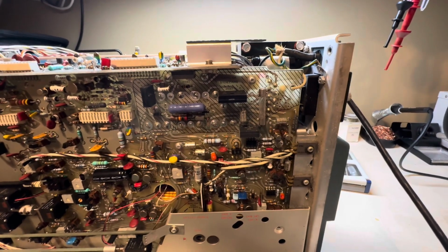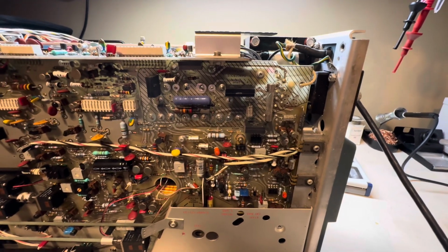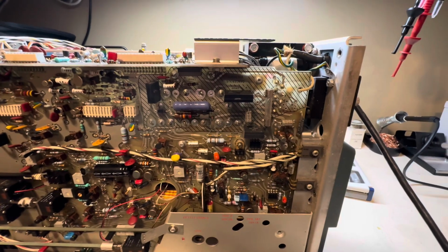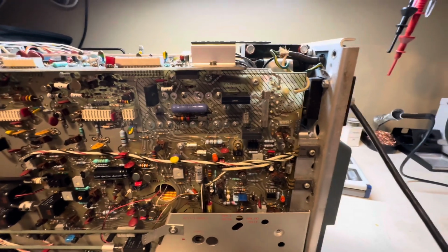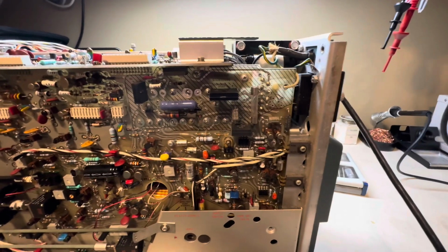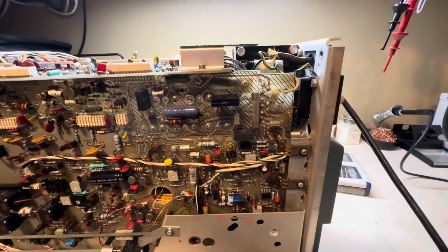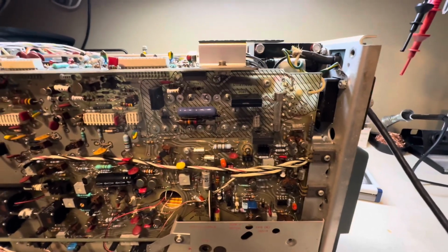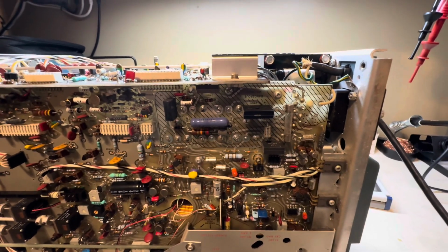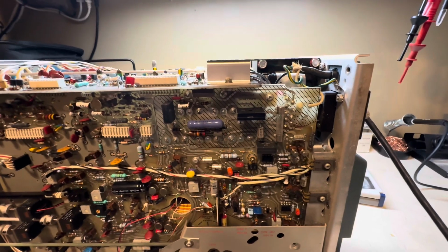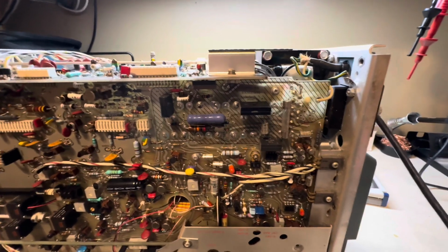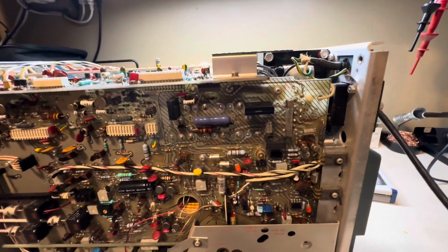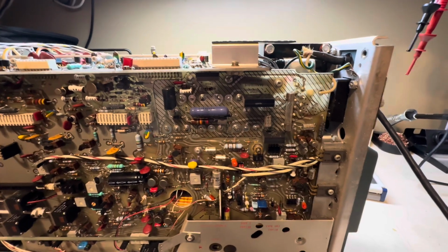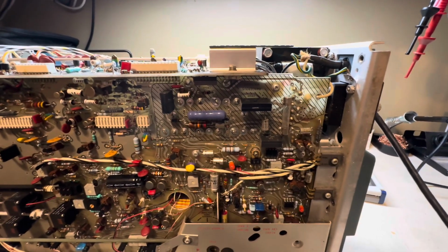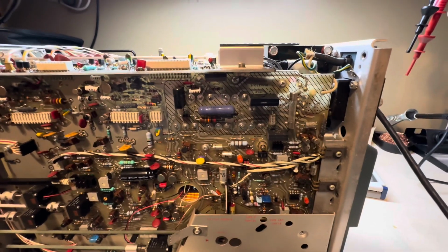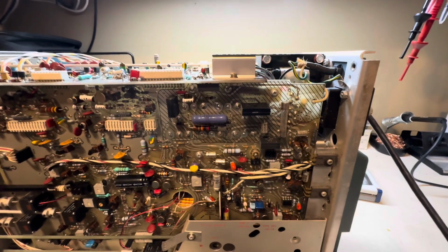Unfortunately, with newer equipment nowadays, they give you block diagrams, and you'll be lucky to even get a block diagram. And when they do give you a block diagram, it's pretty much, okay, if this is doing this and this is doing this, it'll give you steps to take. Then it's going to lead you to this board, and then it's just going to tell you to replace the whole entire board. That's how the service manuals are nowadays compared to the older service manuals, where it takes you step by step and tells you disconnect this, check the voltage on this, check to see if there's a short on this, and then if there is, go to this, until you find where the problem is and where the fault is. That's why I love working on this older equipment, because it's a lot easier to service when you have a full manual and full schematics, of course.